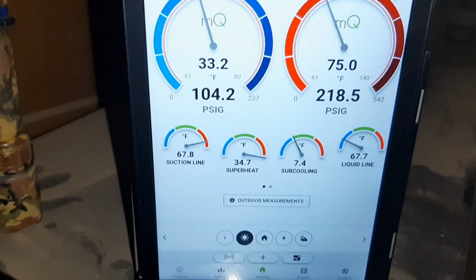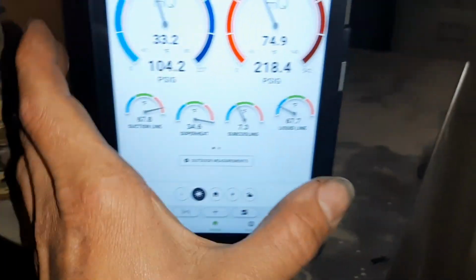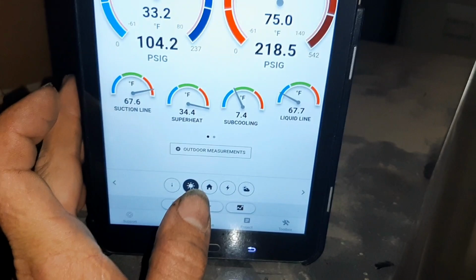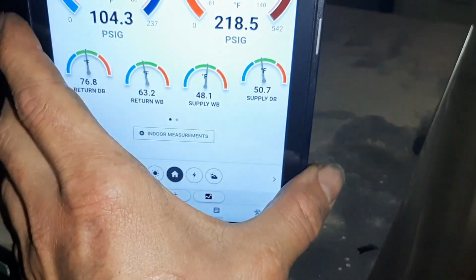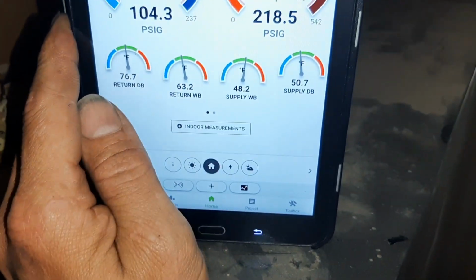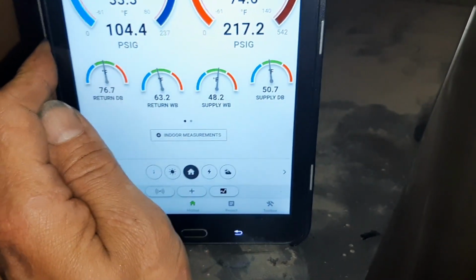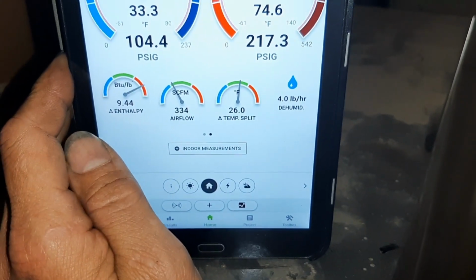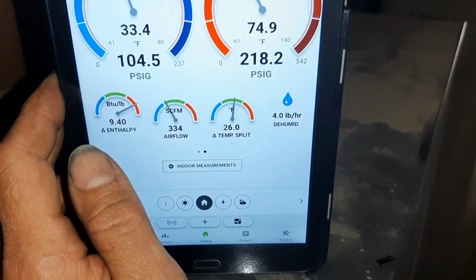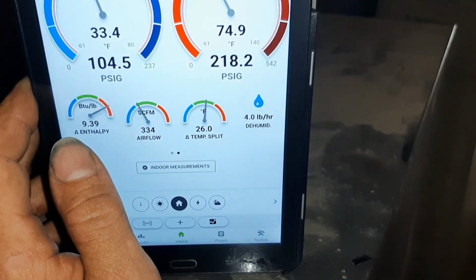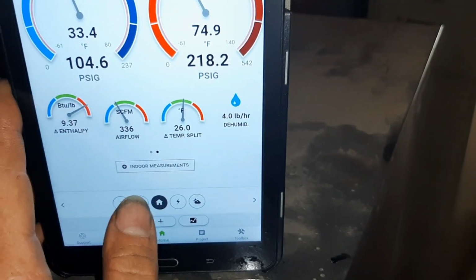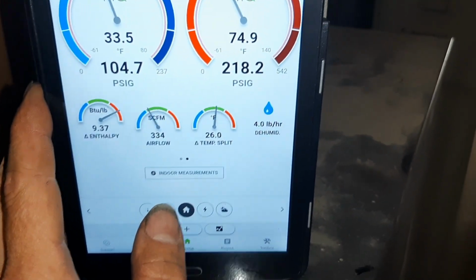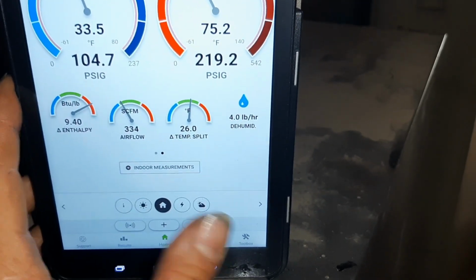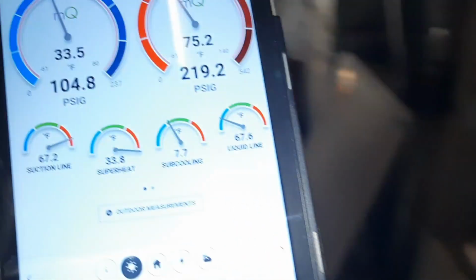Suction looks better. Superheat's coming down. Subcooling's reasonable. Let's see what kind of temp drop we got. Yeah, we got a 26-degree drop. That's going to be just because of our airflow. This thing was put in destined to have problems the way they put it in.